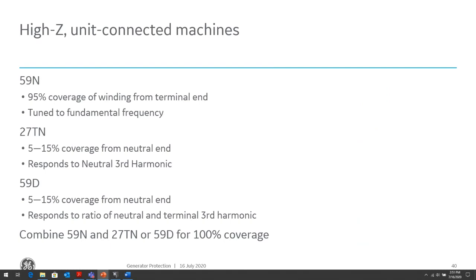The 27TN is a third harmonic undervoltage element. We'll talk a little bit about how that works, and it will also protect for ground faults within the generator. And the 59D is similar to the 59N, except it's a differential, so it's a neutral voltage differential. We'll talk about the advantages of using the 59D compared to the 59N. Combining these elements, we will get 100% fault coverage for ground faults within the stator.